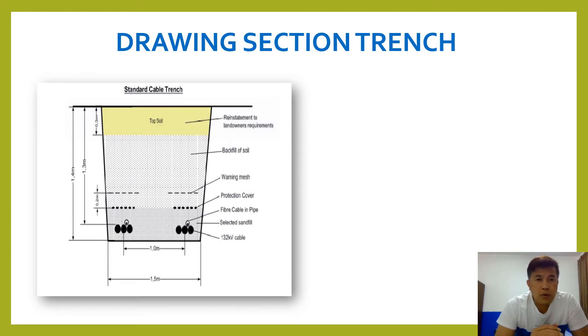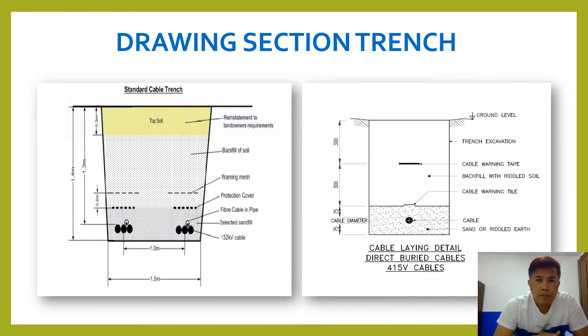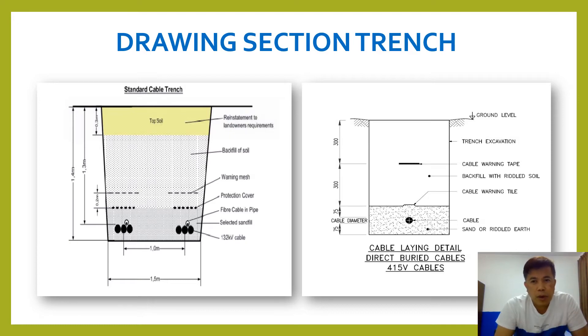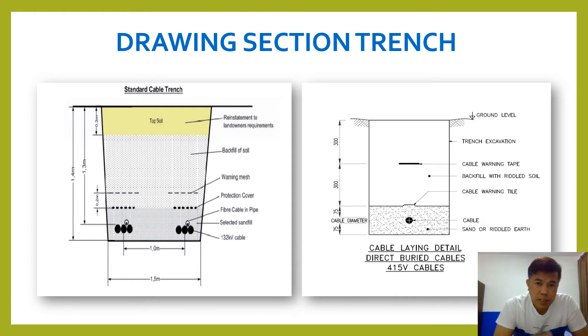The drawing section of the trench — this is how you can see the drawing in your approved drawing. When you are checking drawings outside as a construction engineer or inspector, you can see that drawing. There is a standard and specification for your cables: how they are laid, how you do the backfilling, how you put the cable tile, cable wire, cable tape, and also the interlocking of the cable row identification.